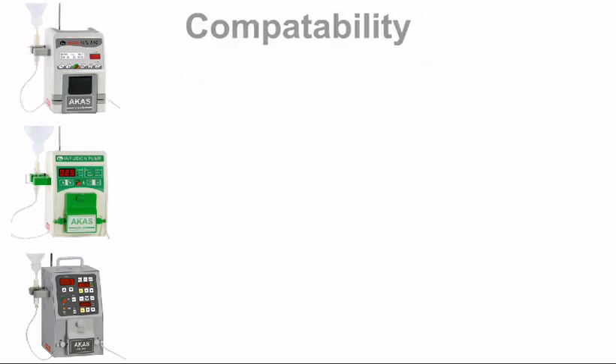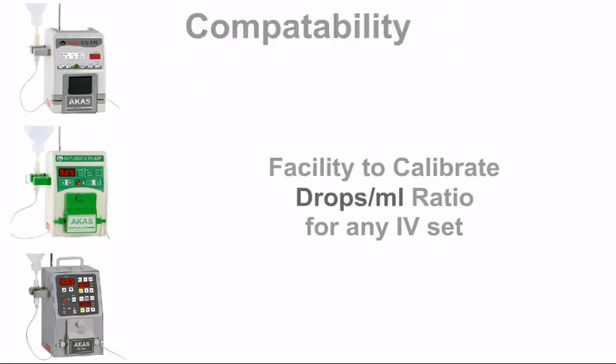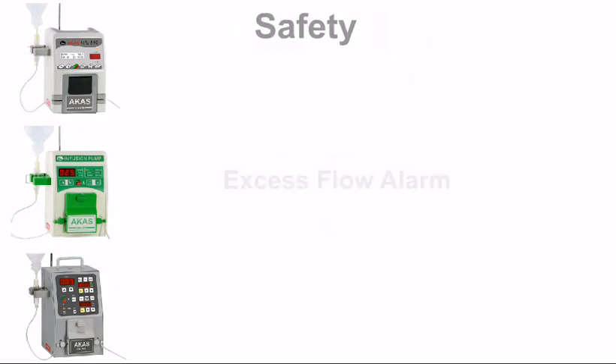Akas infusion pumps can be calibrated to any IV tube and still deliver accurately. Safety alarms are generated for excess flow, less flow, accidental door opening, damaged tubing, pump malfunction, and low battery.